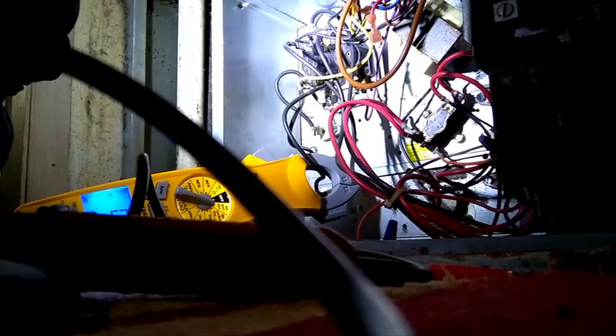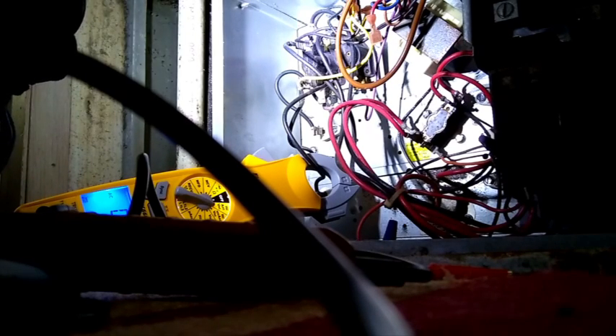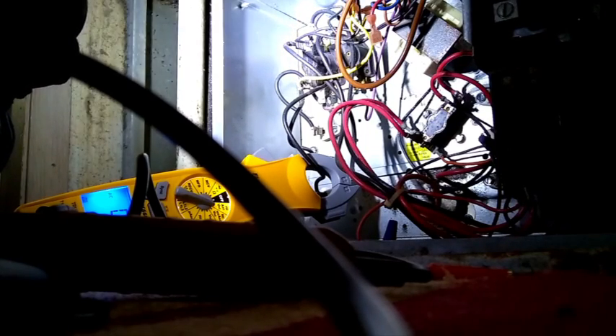A lot of times these things stick, and you'll tap on them, just like the relays from before. You tap on it and it'll start working, then it won't work again, or it'll run constantly, or never come on. These things are the same way—they'll get stuck on constantly, where the blower will just heat until you have to shut it off at the breaker, or it will never come on, which is the issue you have now.